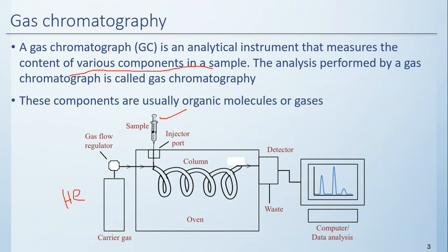So, the carrier gas contains inert gases, and into the high-velocity stream of inert gas, we are injecting a sample of air whose quality is to be checked. And this mixture flows through a helical structure called a column. Inside the column, the components of the sample get separated.